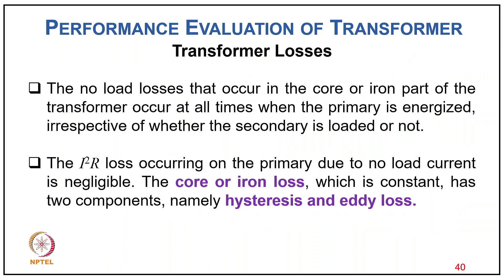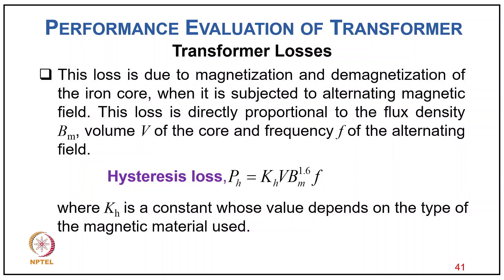The no-load losses occurring in the core occur at all times when the primary is energized, regardless of whether the secondary is loaded or not. The I²R loss in the primary due to no-load current is negligible. Core or iron losses are constant and have two components: hysteresis loss and eddy current loss — both due to magnetization and demagnetization of the iron core under alternating magnetic field, proportional to flux density Bm, volume, and frequency f.